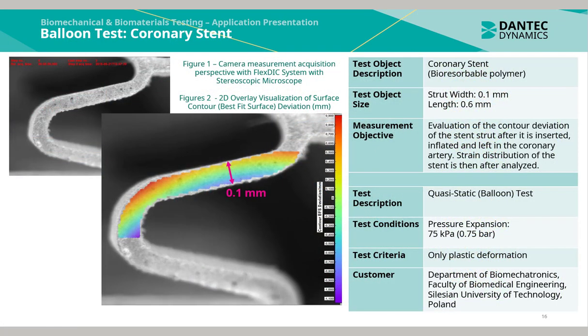This is an application example taken from the cardiac surgery elements. Pictured here using the stereoscopic microscope and the FlexDIC system is a coronary stent. The coronary stent is tested using a balloon expansion test, whereby a balloon is inserted within the stent and expanded, causing the stent to plastically deform.